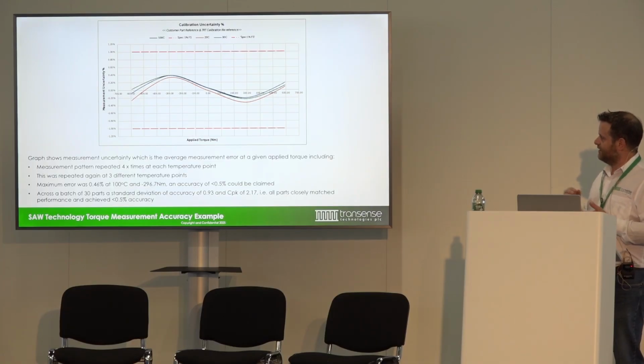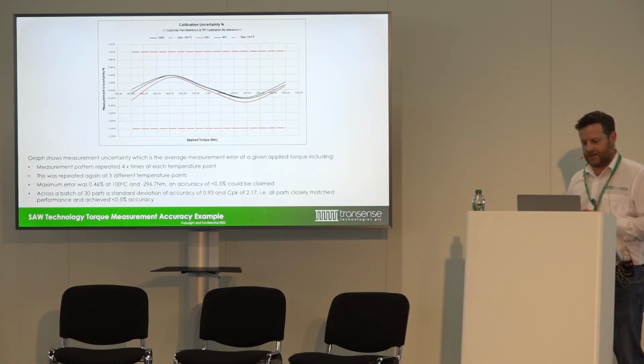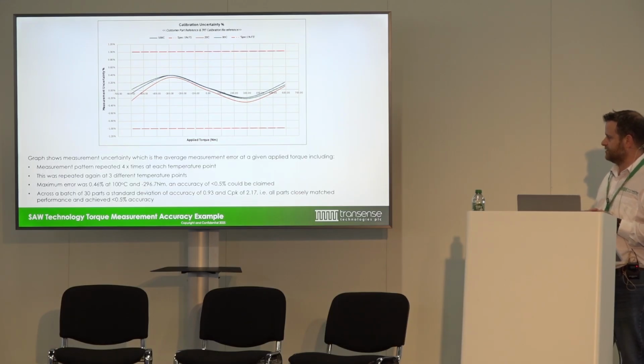We have some examples here showing measurements at different temperatures. Basically the torque that we're applying, and then the uncertainty level that we're getting out of that based on the measurements that we're seeing, i.e. the accuracy level. You can see that we're consistently achieving better than 0.5% here through the various temperature ranges that we're applying the torque at. The maximum error that we're getting is 0.46% at 100 degrees. That's a pretty high temperature, and actually a very good level of accuracy to be achieved.